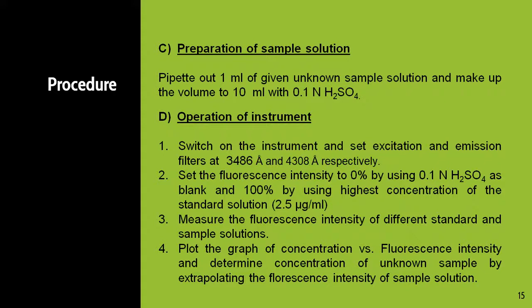To operate the instrument, switch it on and set the excitation and emission filters — that is primary and secondary filters — at 3486 angstroms and 4308 angstroms respectively. First, set the fluorescence intensity to 0% using 0.1 normal H2SO4 as blank. Then set fluorescence intensity to 100% using the highest concentration of the standard solution, which is 2.5 micrograms per ml.